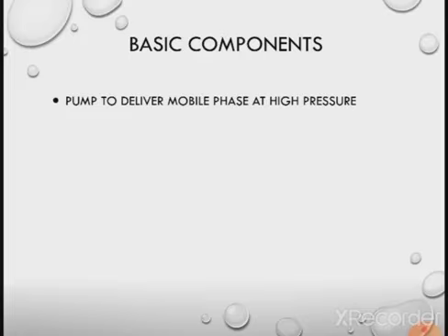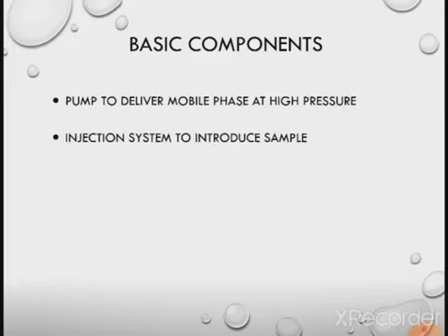Now the next part we want to learn is the injection system. The injection system is very important and is required to introduce the sample. As we know, the pump is providing very high pressure, and in that high pressure we want to introduce the sample without disturbing or reducing the pressure, and that's why we require a special injection system to introduce the sample, and this system is known as a Rheodyne system.